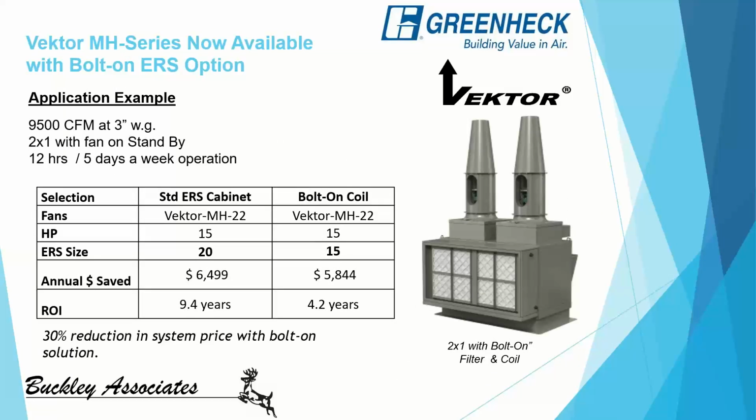Another energy recovery option for the smaller systems is we've now added a Vektor MH series with a bolt-on ERS option, and this is good up to 15,000 CFM. And what you'll notice in that picture there is, for these smaller systems, we've gone away from that big energy recovery box, because on flows below 20,000 CFM, the payback on an energy recovery system just doesn't really make sense. So what we've done is made that option a lot more economical with this bolt-on option.